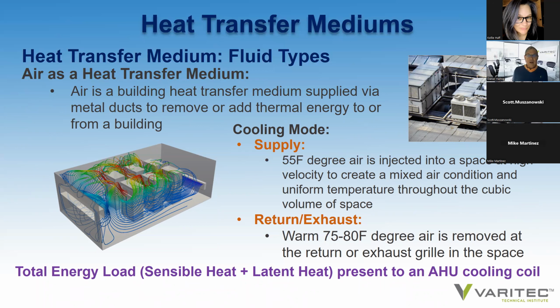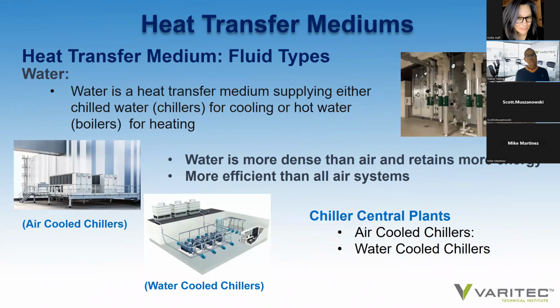Air that absorbs energy in the space will reach 75 to 80 degrees within the space, and is consequently removed through return and exhaust grilles in the space. The total energy load of a building is the sum of the sensible heat and the latent heat. So the total load is a combination of the sensible and latent heat, and that total load in conventional HVAC systems is seen at an air handler cooling coil.